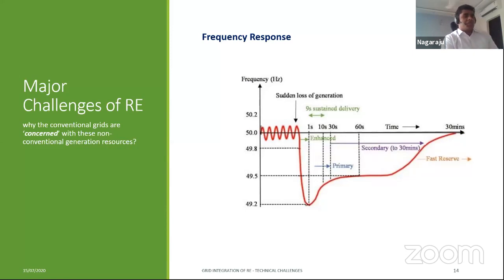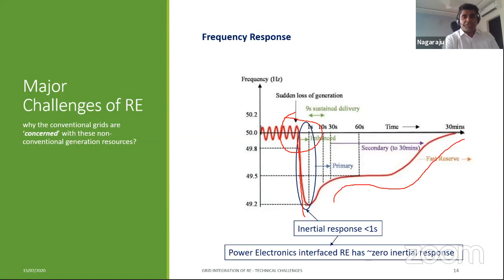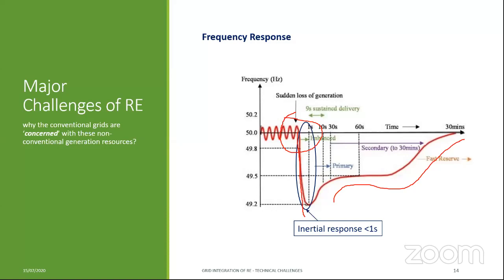The frequency. This is a well-known picture. I'm sure you must have seen this. So this shows the grid frequency variation upon loss of a generation. So here, a sudden loss of a conventional machine would lead to an abrupt fall in inertia. And then how quickly it can come up and to what level depends on the interfaces, or on making the renewable energy sources help the grid. Because the source is decoupled, we have almost zero inertia response for some types of renewable energy which are prominent, like PV, right?